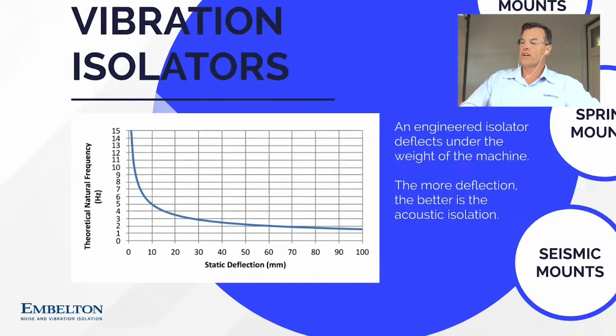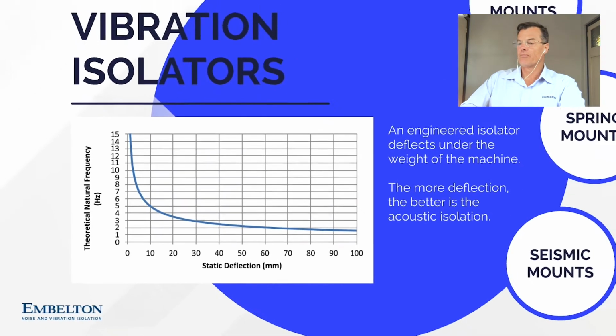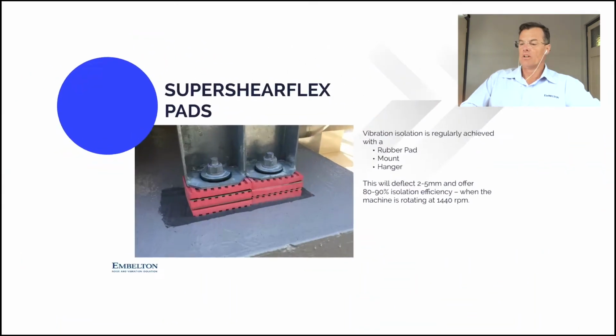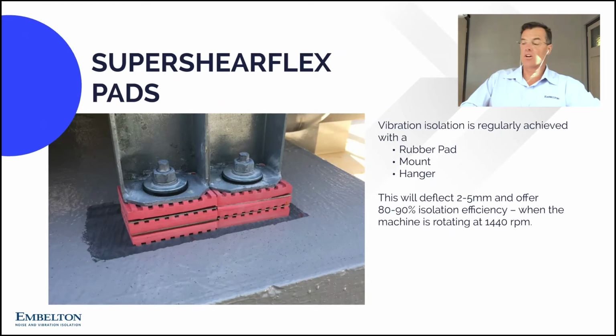As you can see from the table here, the more you deflect an isolator, the lower its natural frequency, therefore achieving better acoustic isolation. Super shear flex are rubber pad isolators. They deflect 2 to 3 millimeters or more if they're layered and can achieve 80 to 90% efficiency at isolating a 4-pole electric motor.